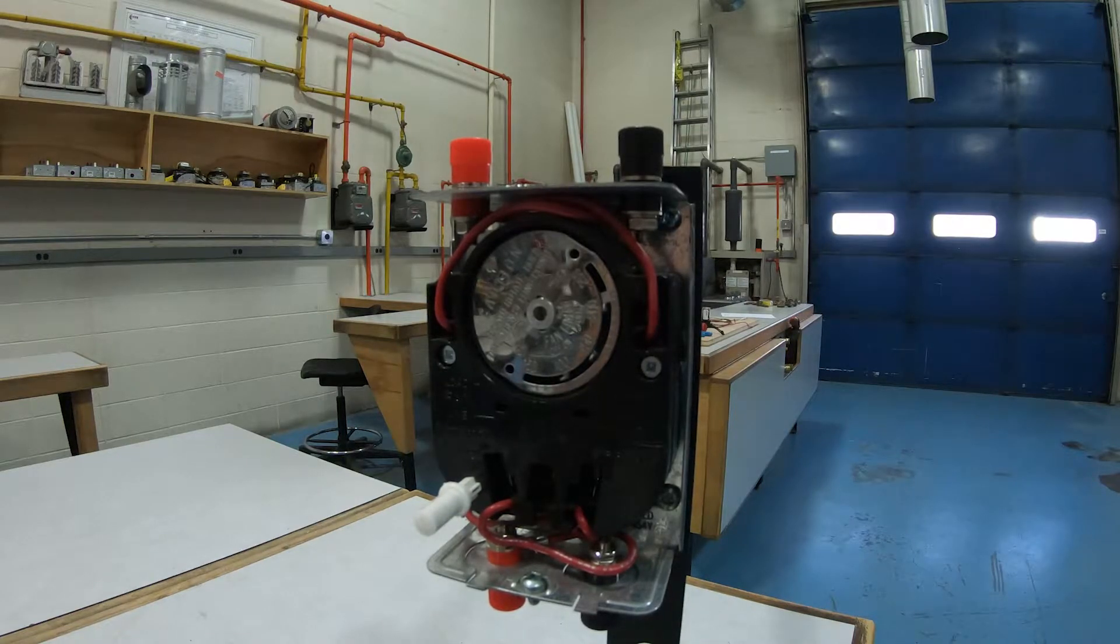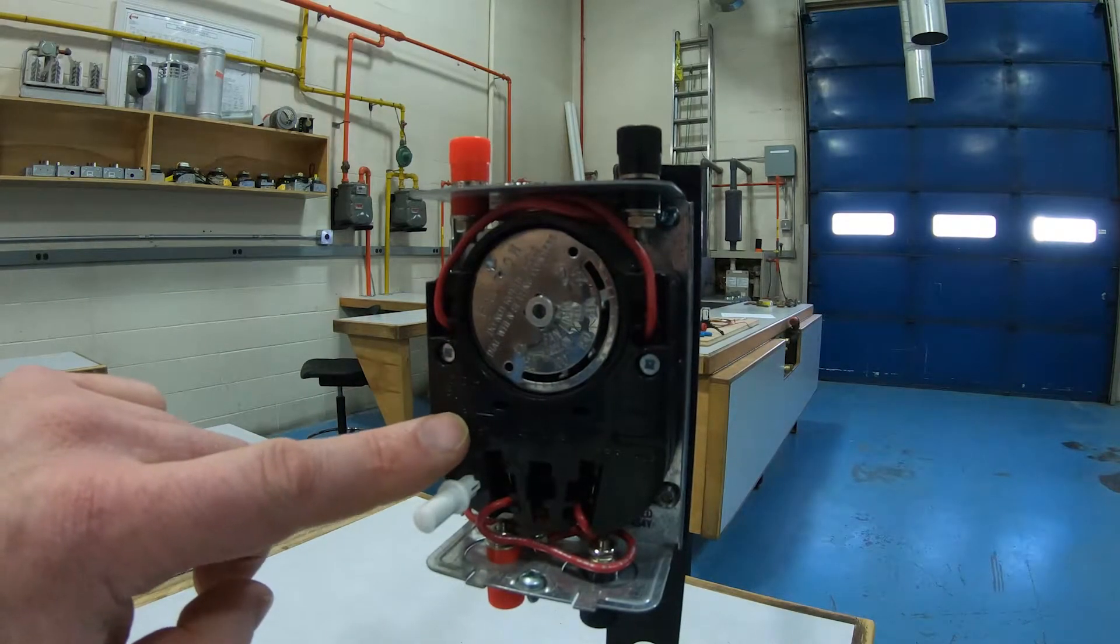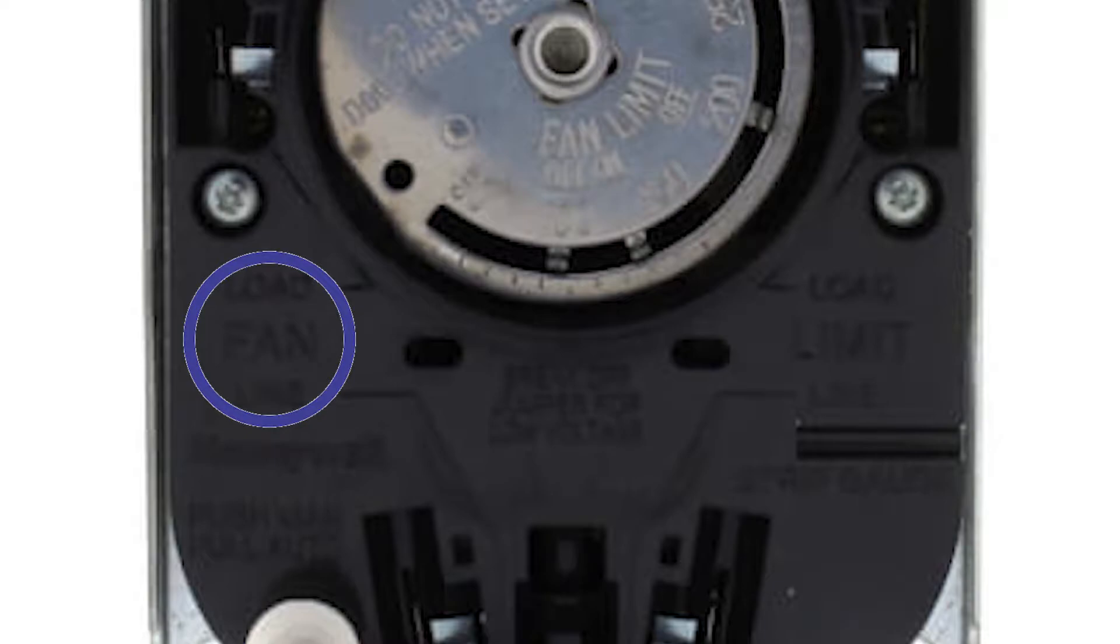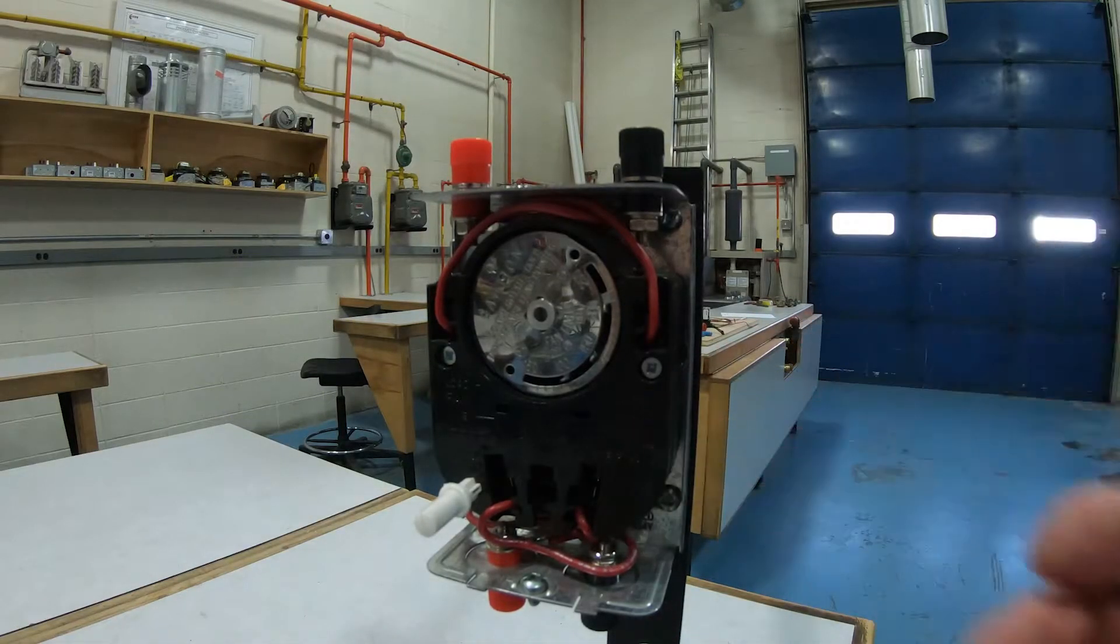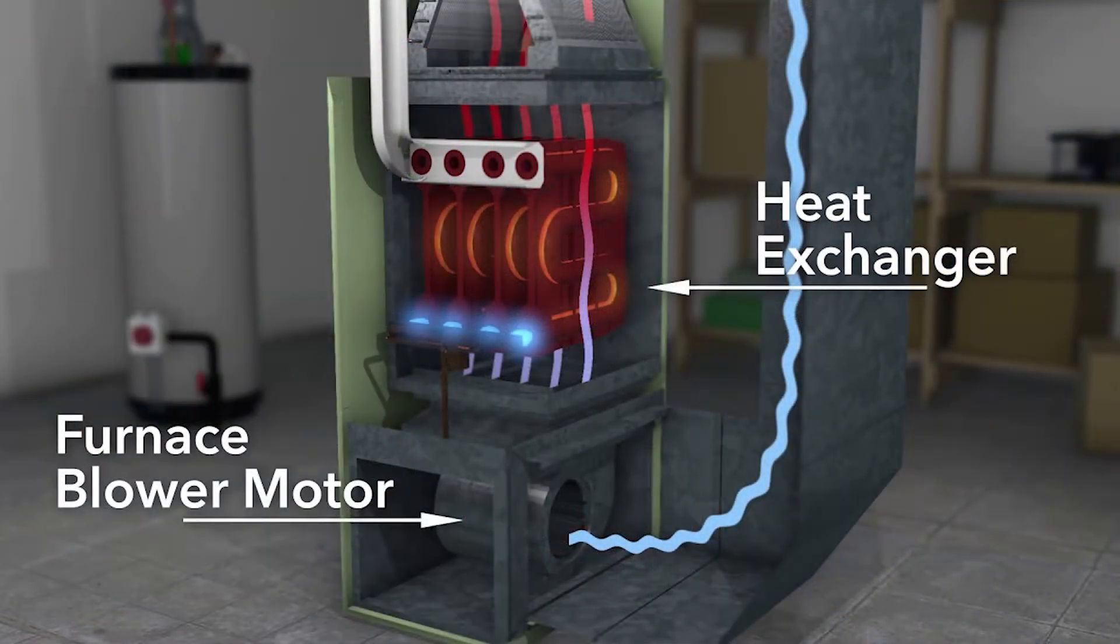First of all is the fan side, you can actually see labeled fan there. I may need to show you a close-up with this picture. The other side over here is the limit side. The fan side will turn the blower motor or the blower fan off and on in the furnace. The blower motor only comes on when it's hot enough and then it'll shut itself off again when it's cool enough.